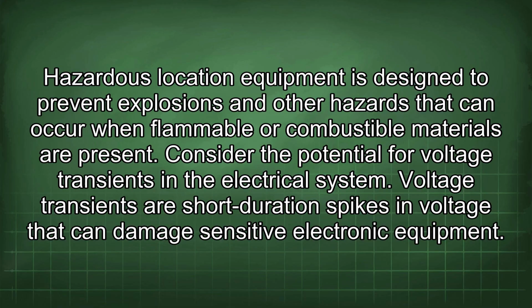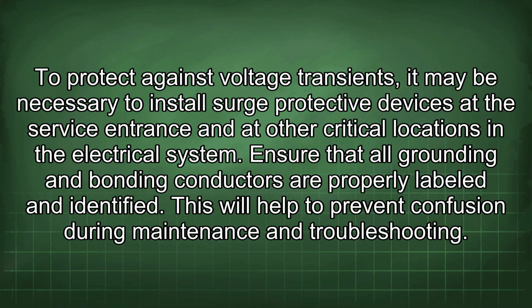Consider the potential for voltage transients in the electrical system. Voltage transients are short-duration spikes in voltage that can damage sensitive electronic equipment. To protect against voltage transients, it may be necessary to install surge protective devices at the service entrance and at other critical locations in the electrical system.